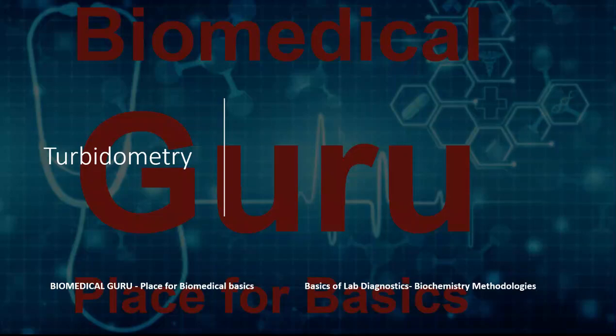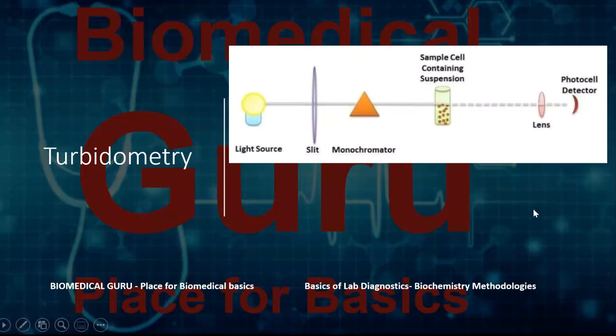Then comes turbidometry. So what is turbidometry? Turbidometry is very similar to photometry or colorimetry, but the only difference is that the color is not changing here. The light source will remain the same, the optics will remain the same, the filters or the monochromator will remain the same, but here we analyze the amount of light that is deflected or deviated.